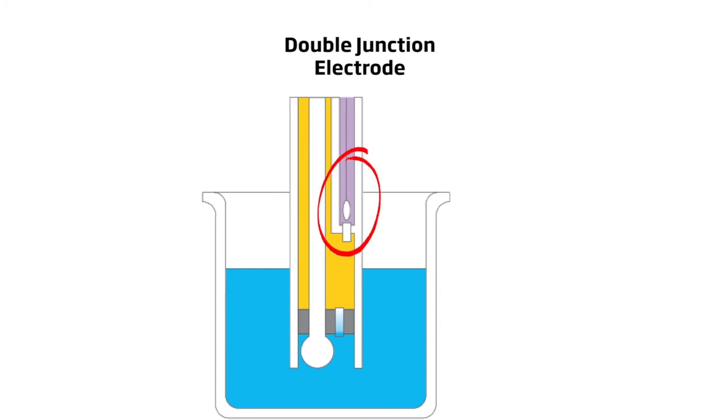The chamber that contains silver chloride houses the reference wire and is connected to the second chamber through a junction, but is not directly connected to the sample. The second chamber is directly connected to the sample and contains only 3.5 molar KCl electrolyte.